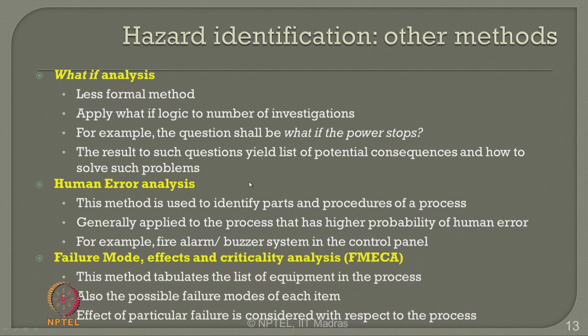The third one, of course the most important one, is a hazard identification method which is FMECA, failure mode, effects and criticality analysis. This is a highly formal method which tabulates a list of equipment in a given process. It also finds out the possible failure modes of each item present in the process plant, and the effect of a particular failure is considered with respect to the process as a whole. So, this gives me a detailed diagnosis of failure at the component level as well as at the product level.